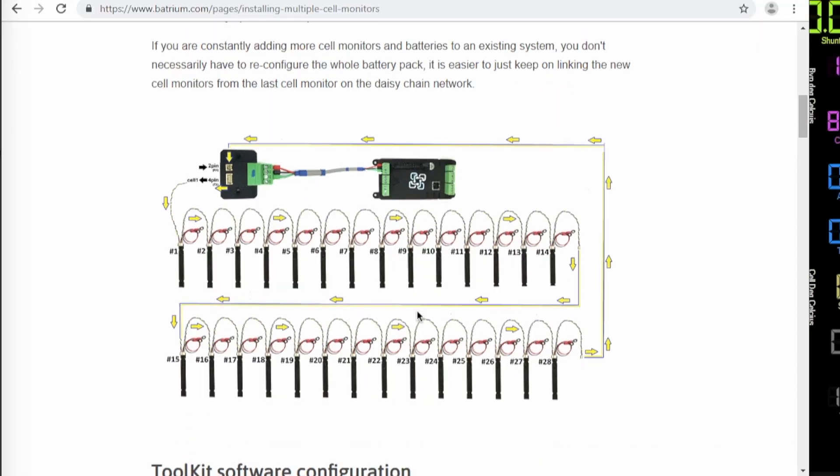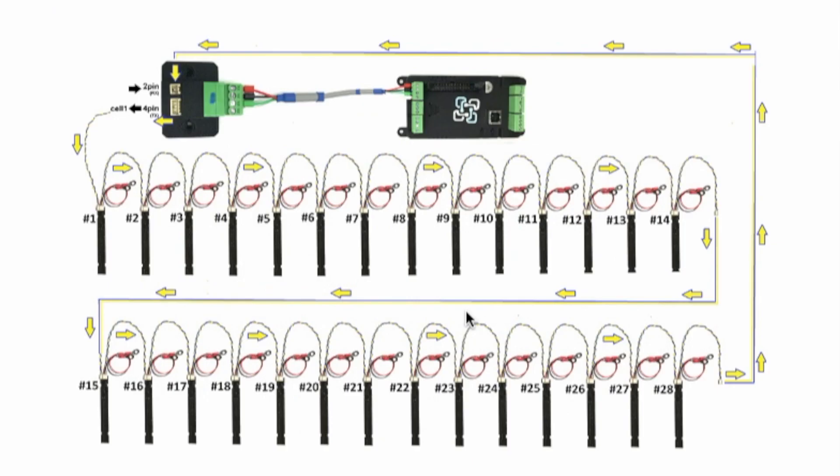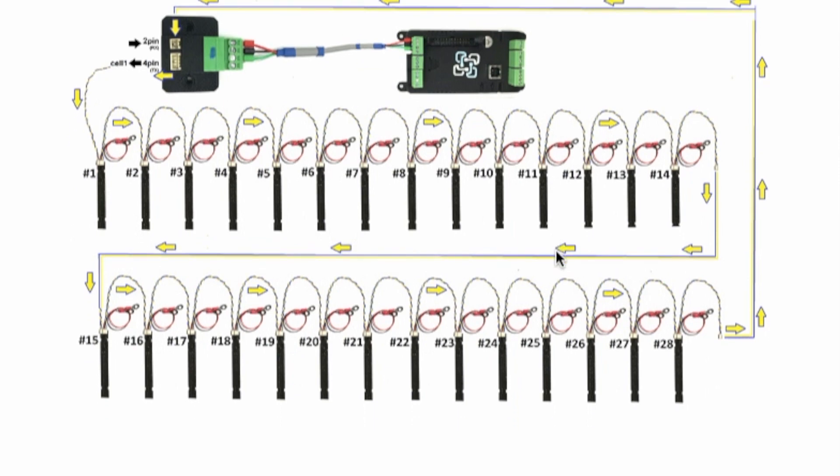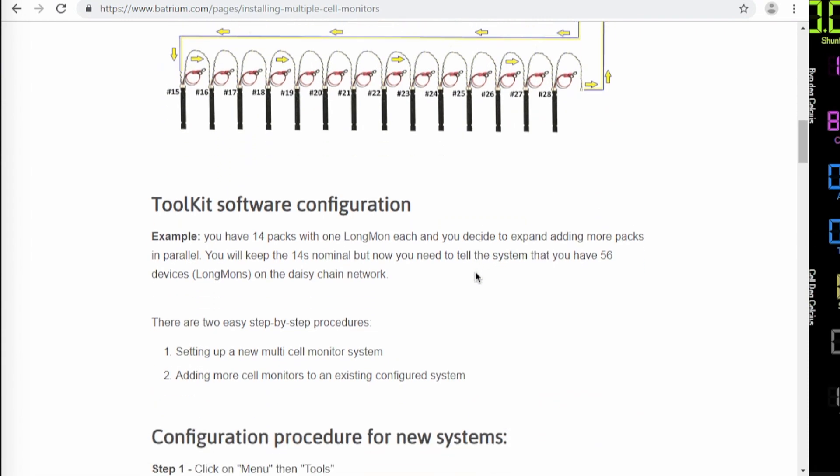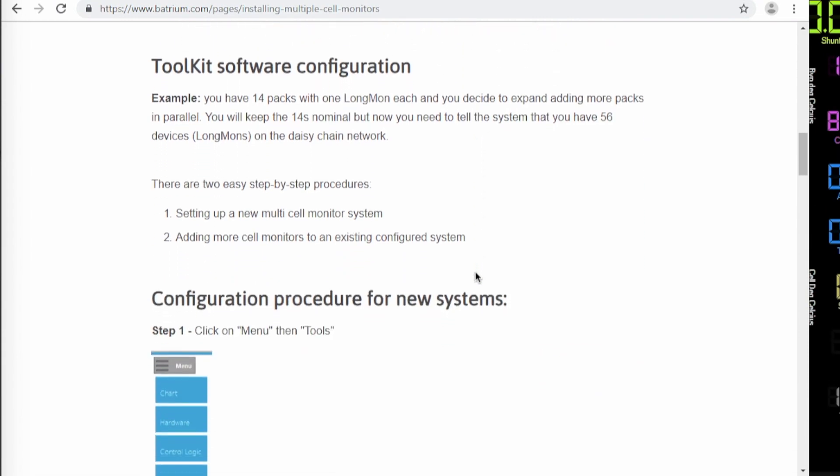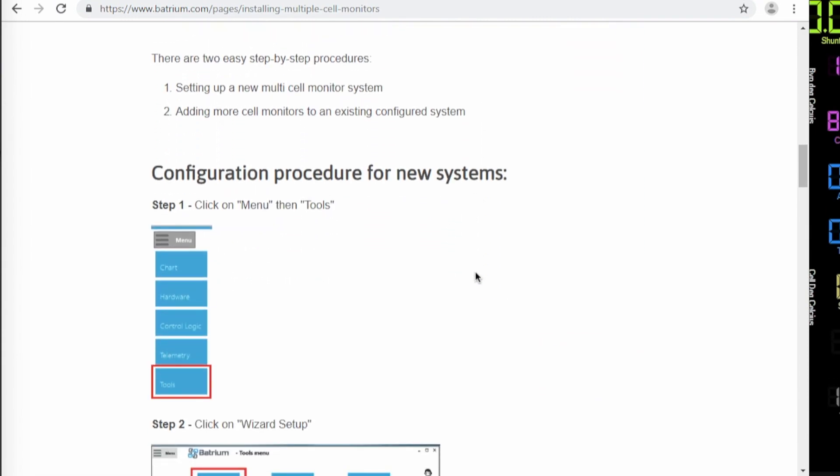This is the picture. It actually illustrates exactly the setup we have here at the moment. Two battery packs connected to the same WatchMon Supervisor. So you see it talks through the first 14 cell monitors back and then another 14 cell monitors back to WatchMon Supervisor. And then you have two different ways to configure this.